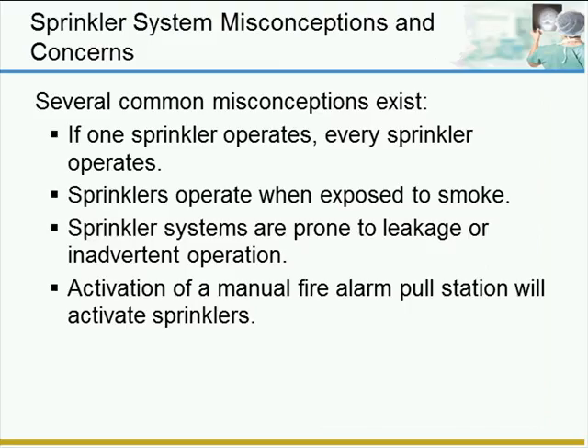There are several misconceptions concerning sprinkler systems, and I'll just go over those quickly. If one sprinkler operates, every sprinkler operates. That is not true, on a system that you would see typically in a healthcare facility or hospital. Sprinklers do not operate when they're exposed to smoke. Sprinklers, when properly maintained, are not prone to leakage or inadvertent operation, and manual pull stations do not activate the sprinklers.